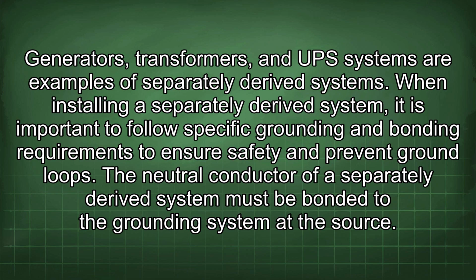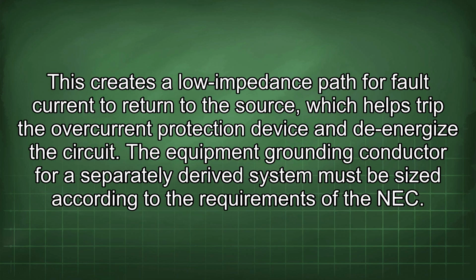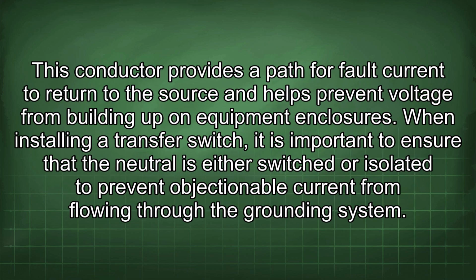The neutral conductor of a separately derived system must be bonded to the grounding system at the source. This creates a low impedance path for fault current to return to the source, which helps trip the overcurrent protection device and de-energize the circuit. The equipment grounding conductor for a separately derived system must be sized according to the requirements of the NEC.